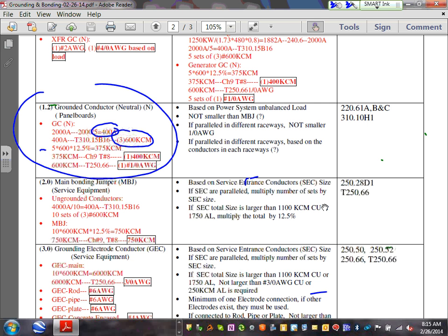Then you do the same thing: 5 times 600 times 12.5%, gives you 375. Take this one to Table 8. That will give you either your neutral can be 400 kcmil, or if you parallel them in different conduits, you take the 600 kcmil to 250.66, that will get you a minimum of 1/0 AWG. Any comments, any questions? So that would be 5 conductors, each one of them 1/0 AWG.